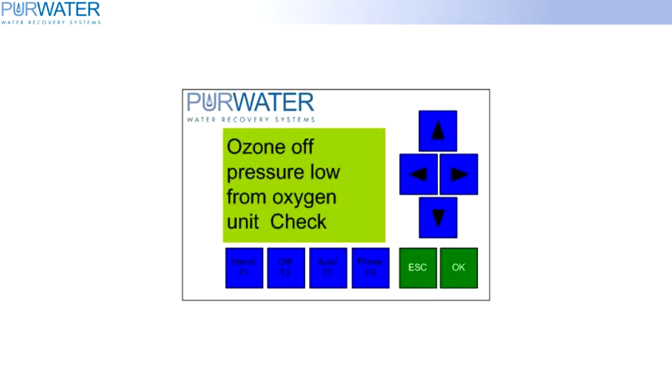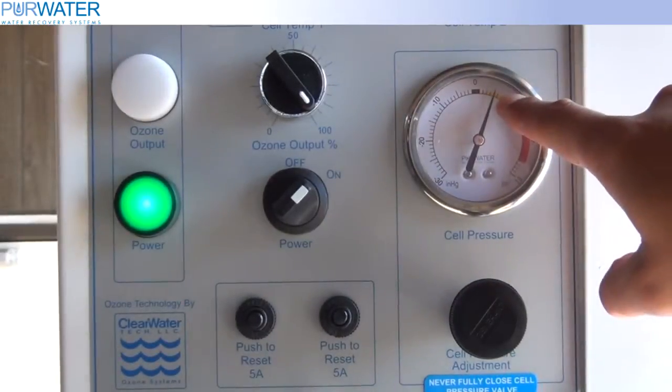If your HMI screen is showing a low pressure fault, the first thing we want to look at is the ozone cell pressure gauge. If your cell pressure is not at 8 psi, use the cell pressure adjustment valve and set the pressure to 8 psi. This should clear the fault and you should start producing ozone.